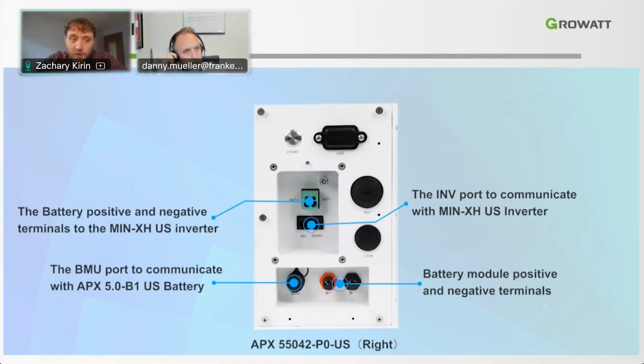It can connect to multiple inverters. You can do multiple inverters per SYN 200, right? Yes, you can. Each one of those inverters could have their own battery system as well. So the max would technically be 90 kilowatt hours of battery per SYN 200, as I understand it. Is that correct? Yes, you have it correctly.